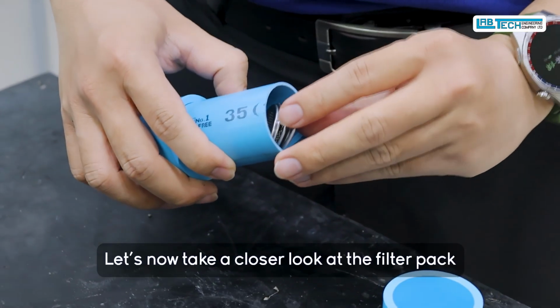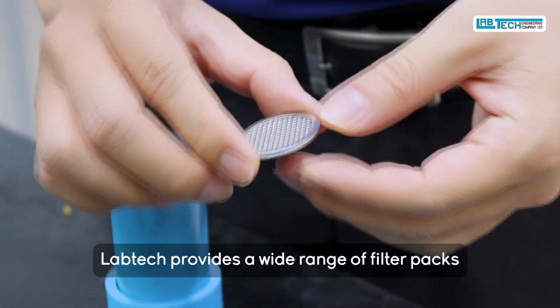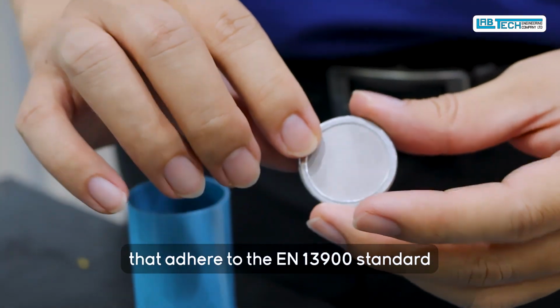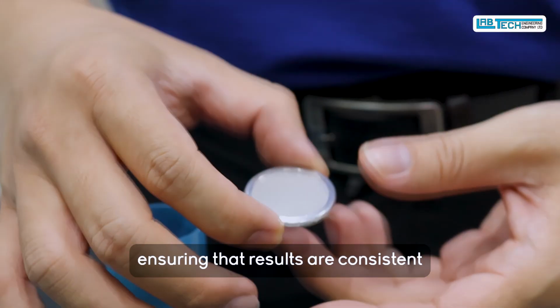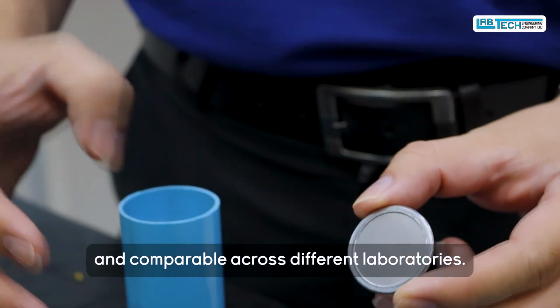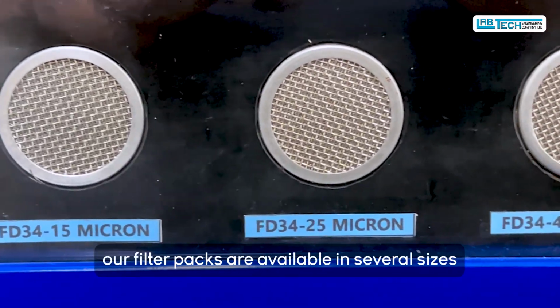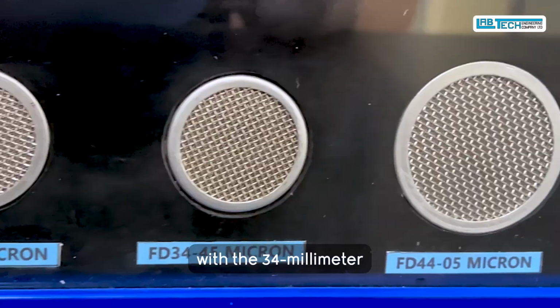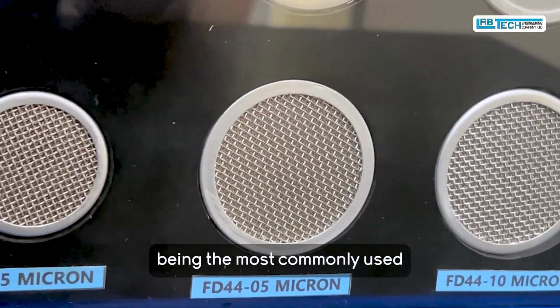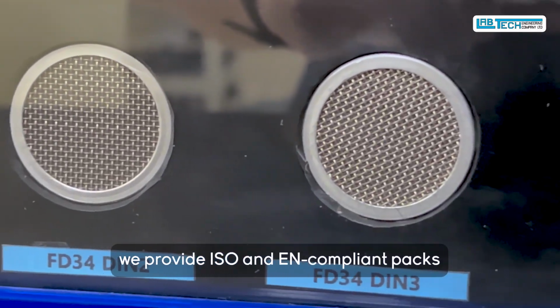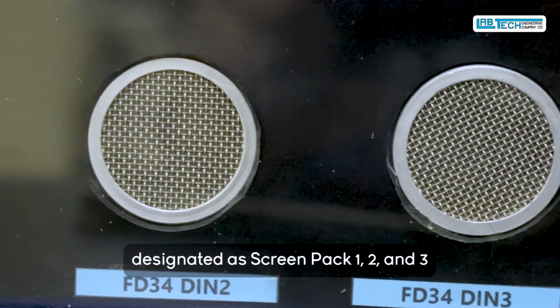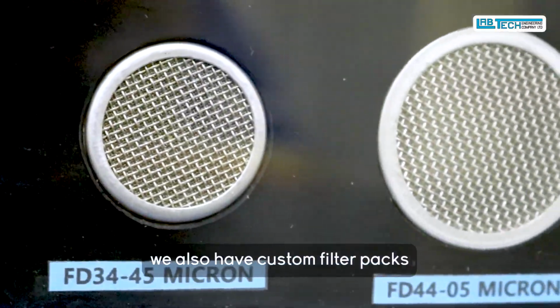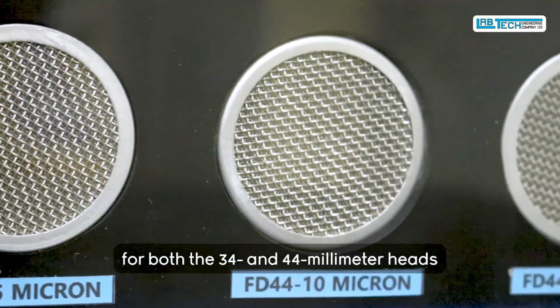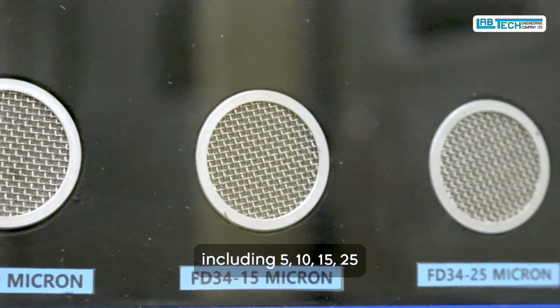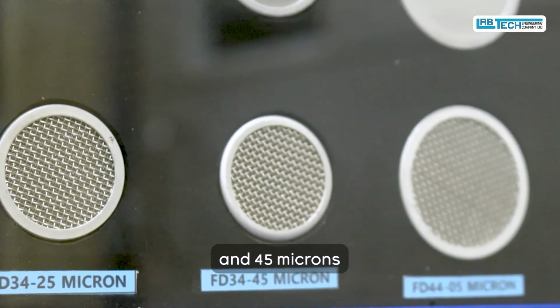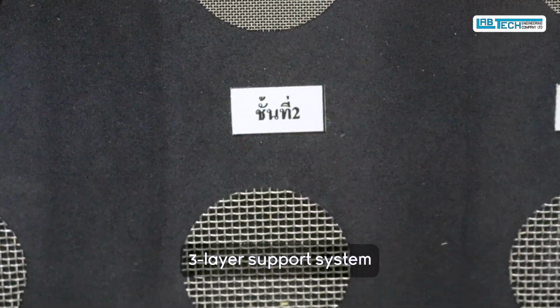Let's now take a closer look at the filter pack, the component that is the very heart of the test. Labtech provides a wide range of filter packs that adhere to the EN 13900 standard, ensuring that results are consistent, repeatable, and comparable across different laboratories. Briefly, our filter packs are available in several sizes, with the 34mm and 44mm models being the most commonly used. For our standard 34mm filter pack, we provide ISO and EN compliant packs designated as Screen Pack 1, 2, and 3. Furthermore, we also have custom filter packs for both the 34 and 44mm heads. These are available in a range of nominal aperture sizes, including 5, 10, 15, 25, and 45 microns. Each of these packs is constructed with a robust 3-layer support system.